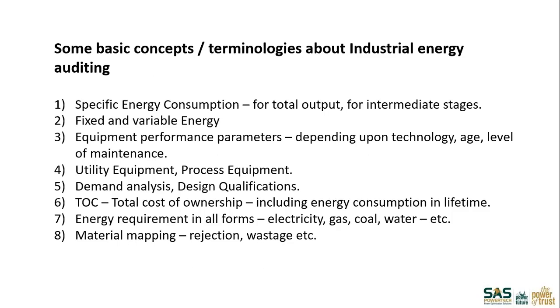Boiler is a boiler. So these kinds of equipment are categorized as utility equipment, and process equipment will be something like, in the case of a hospital, an MRI machine is process equipment. In the case of injection molding, the injection molding machine is process equipment, but the chiller which feeds chilled water to that machine for cooling the die is utility equipment. So you should be able to differentiate between these two.